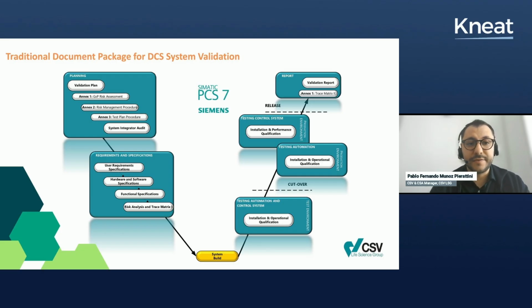And the second step is to define the user requirements, receive the functional, the hardware and software specification from the vendor, and issue the risk assessment and the traceability matrix. And after that, we can verify the different configurations and functionalities of our system. We need to write a protocol, review this protocol, and execute the protocol. So in our case, for the PCS7, we use the cutover approach. We perform the installation and operational qualification in the testing environment, and the installation and performance qualification in our production environment before releasing the system.